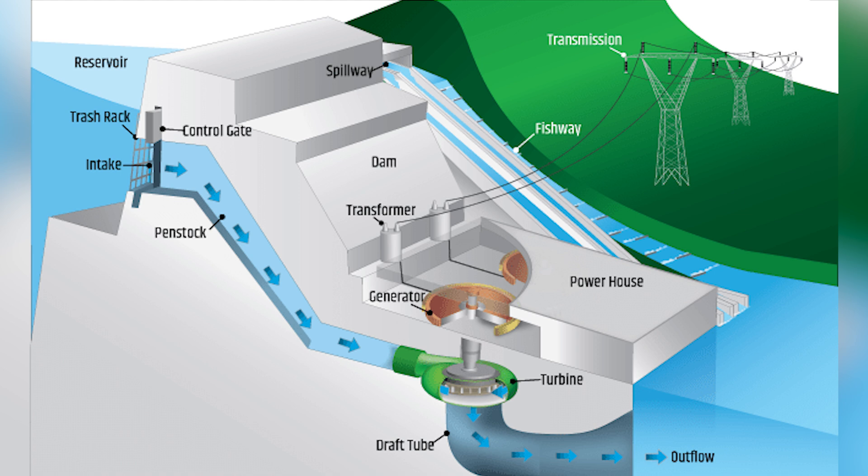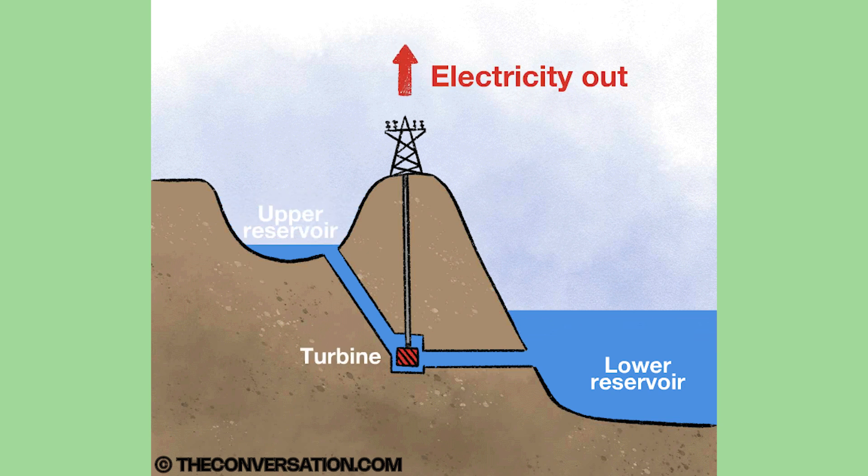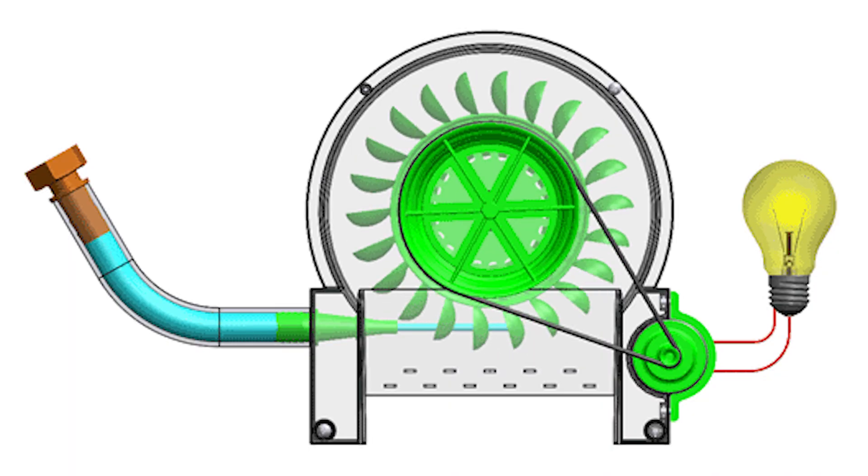This is standard for any hydropower system, but what separates hydroelectric energy storage plants is their ability to return water to the upper reservoir in what we call a recharge, via an electric pump. During periods of high demand, stored water is released through turbines to produce electric power. Whereas during off-peak hours, electric power is used to push water back into the reservoir. Using energy to store energy seems contradicting, doesn't it? In fact, it's not — because against losses due to pumping, pumped hydroelectric storage allows grid operators to increase revenue by selling more electricity during peak demands.